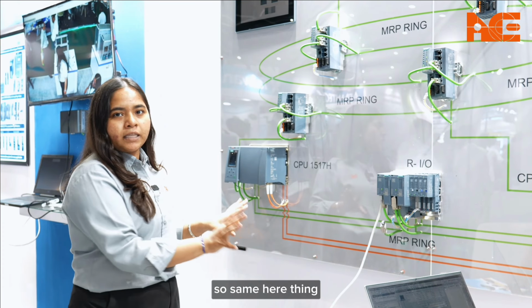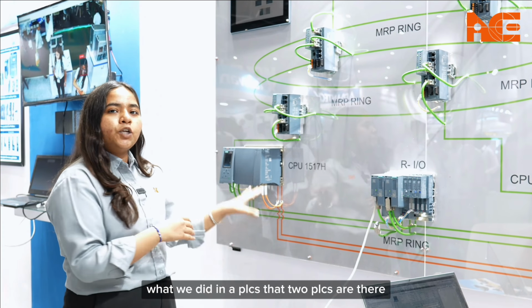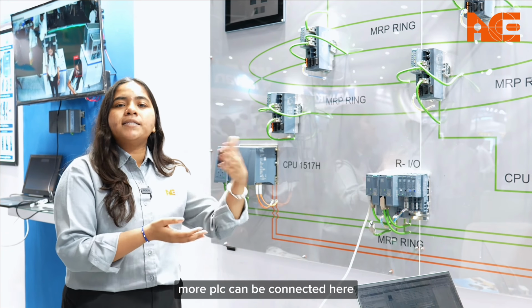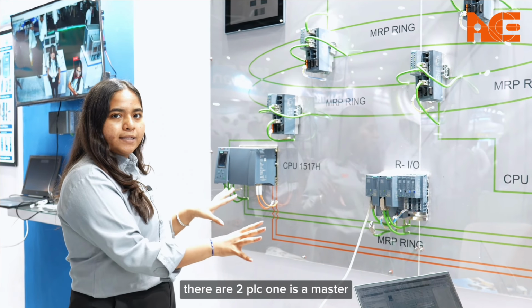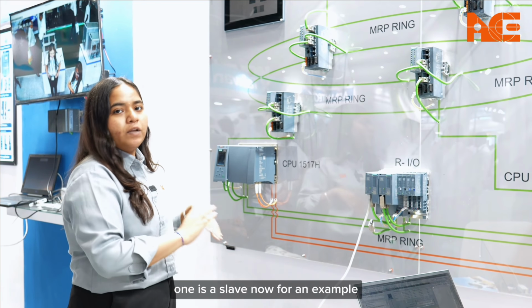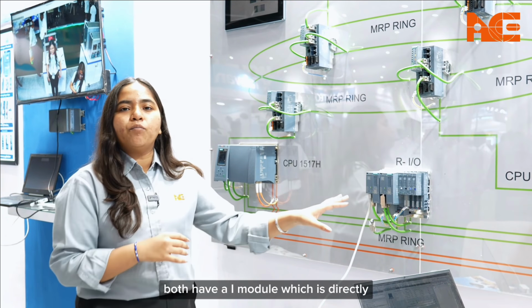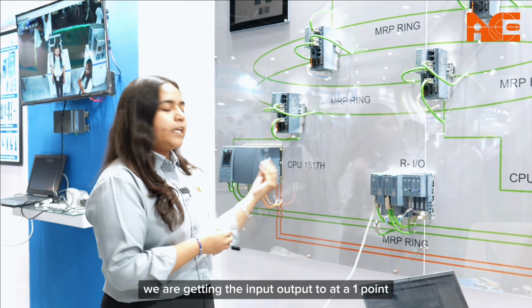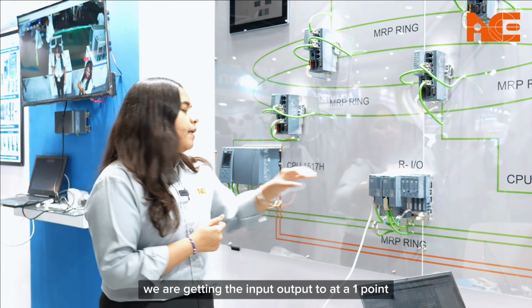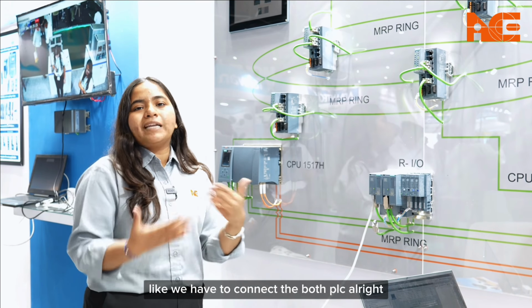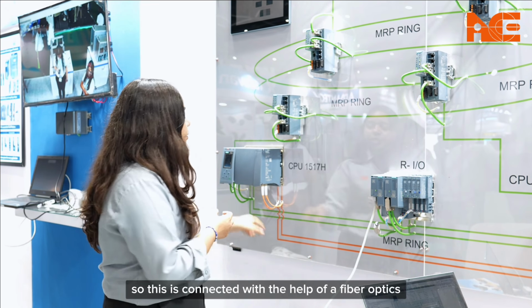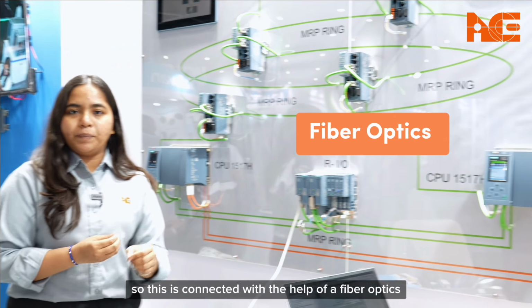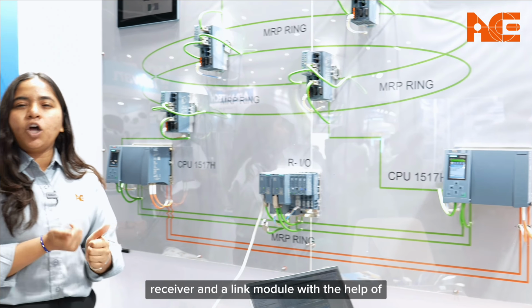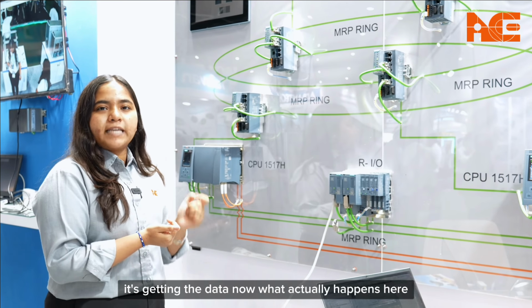We did the same thing with PLCs: two PLCs are there, and more PLCs can be connected. Here there are two PLCs, one is a master, one is a slave. Both have an IM module, through which we get the input and output at one point. Now we have to connect both PLCs. This is connected with the help of fiber optics, which has a transmitter, receiver and a link module, and with the help of that we are getting the data.